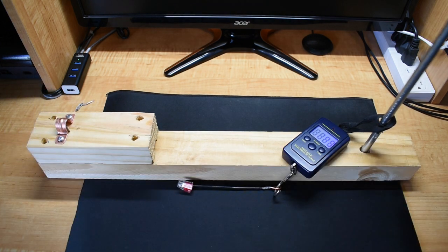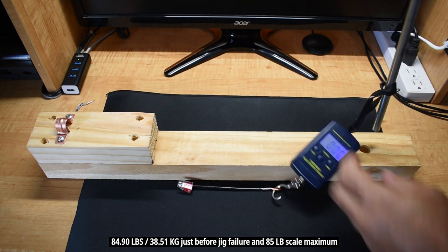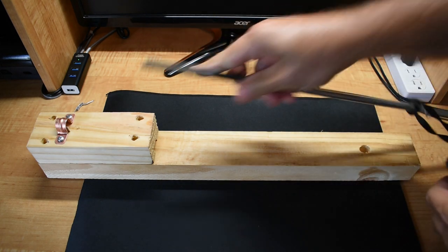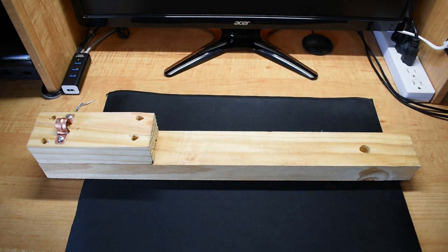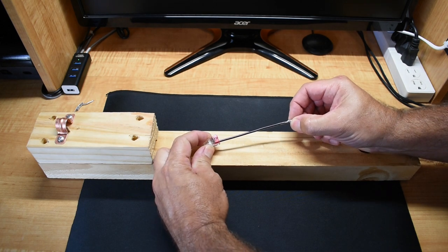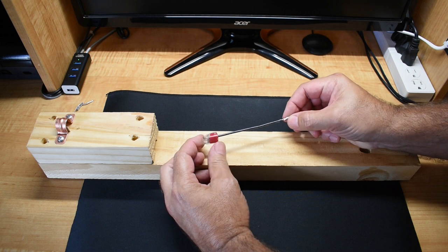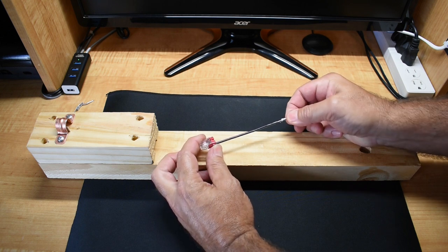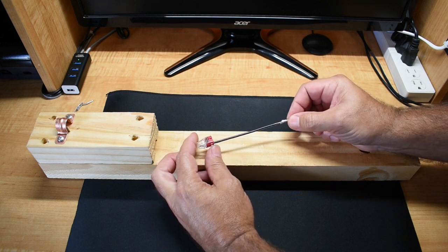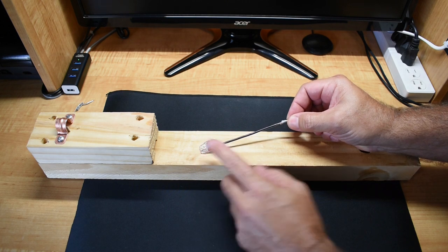Now we're going to be testing a solid conductor using the ideal push-in. Wow! That was some serious power on that one. I have to put a new nail in here. And believe it or not, that wire is still in there. So, it'll exceed 85 pounds using a solid copper wire. Way stronger than using stranded with these connectors.